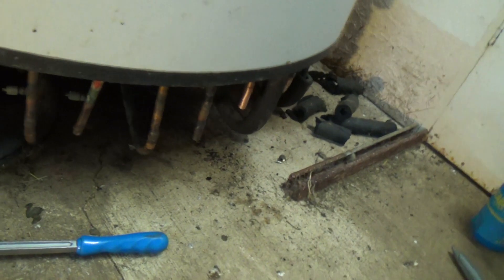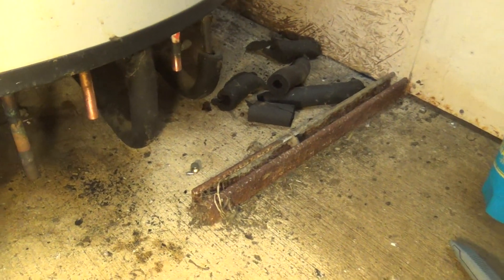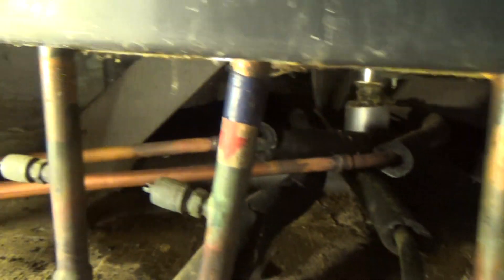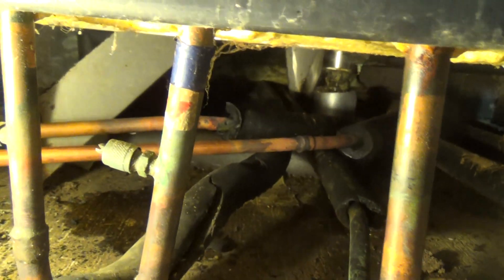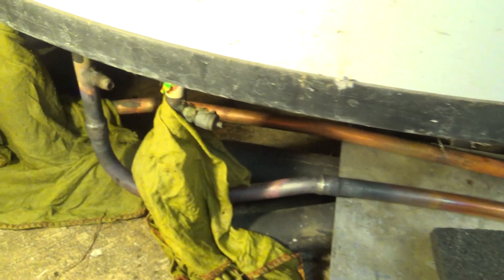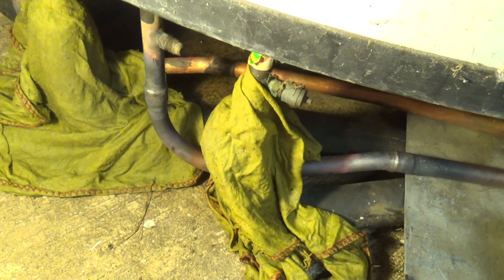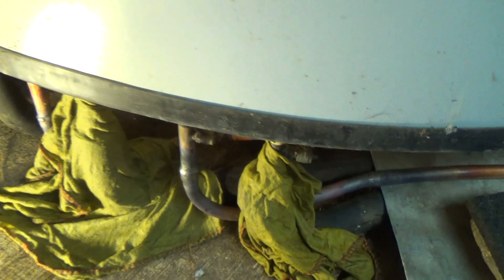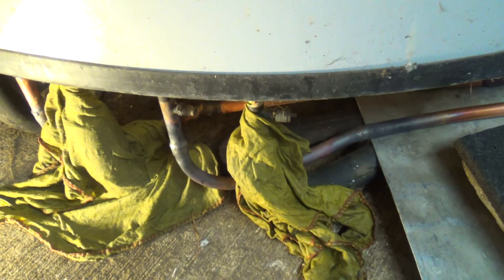Right, got those two pipes - that circuit cut out from that one. And I've extended them with what pipe I had on the van. I could have done with a bit more soft drawn, but anyway. I've used the bends that came off the original ones, brazed them on, so those two are on there. I've got to wait for that to cool down, put a new Schrader core in there and a cap, and then we put it on pressure test. Keep your fingers crossed.